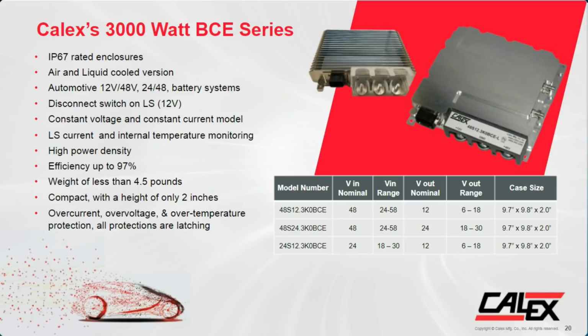You can run 3,000 watts with about 300 LFM at 85 degrees C ambient. In dead airspace, the derating curve—we're still working on the simulation—looks like it will come down to about 1.2 kilowatts at 80 degrees C with no airflow. So it really depends on your application and how much air you're going to move across it.